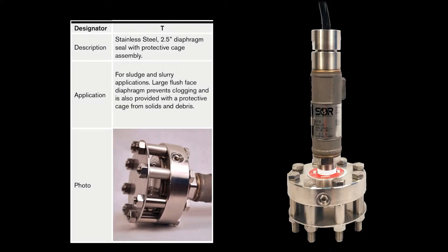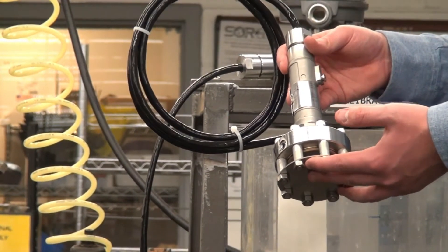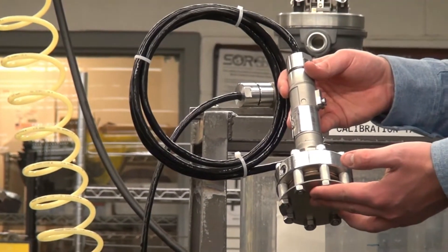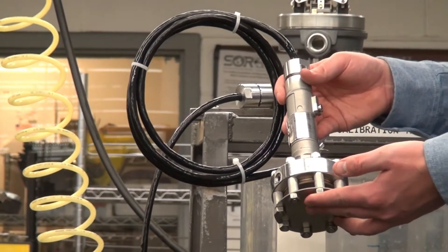The third option we have is a cage diaphragm seal option. The cage diaphragm seal option incorporates a two and a half inch flush face diaphragm seal. This is good for applications that contain sludges or slurries that can potentially build up on the inside of the process connection. This way you can easily clean the face of the surface without any issues.